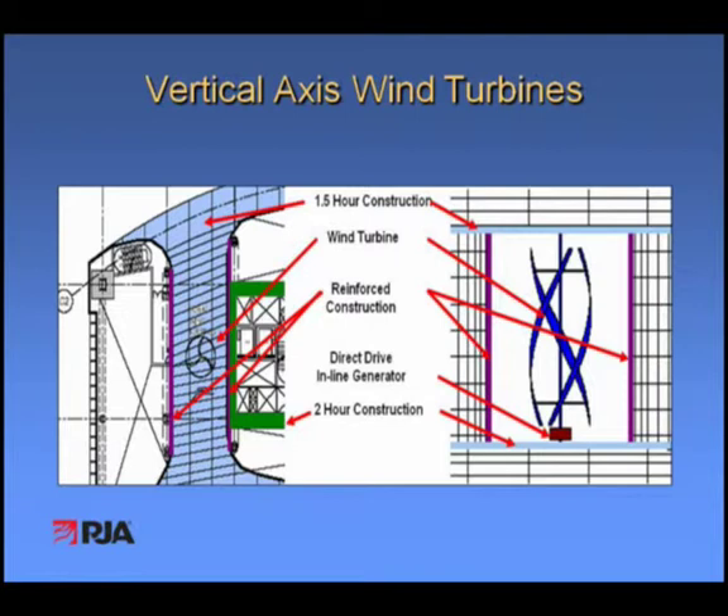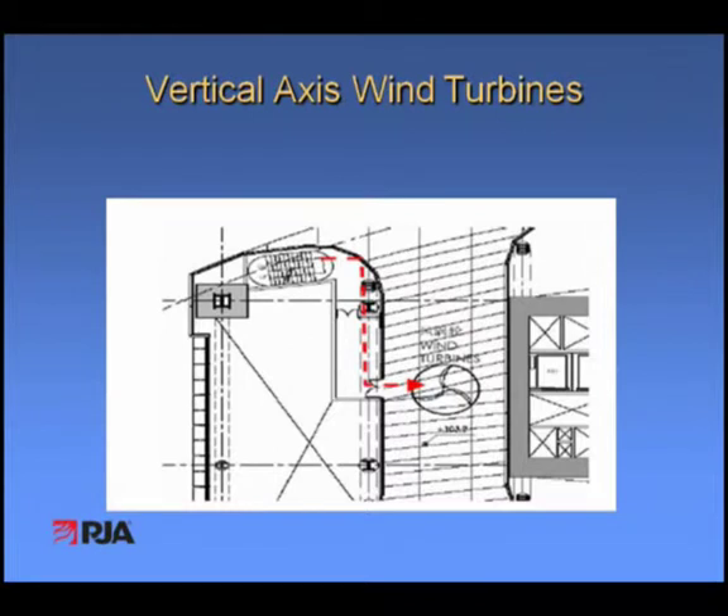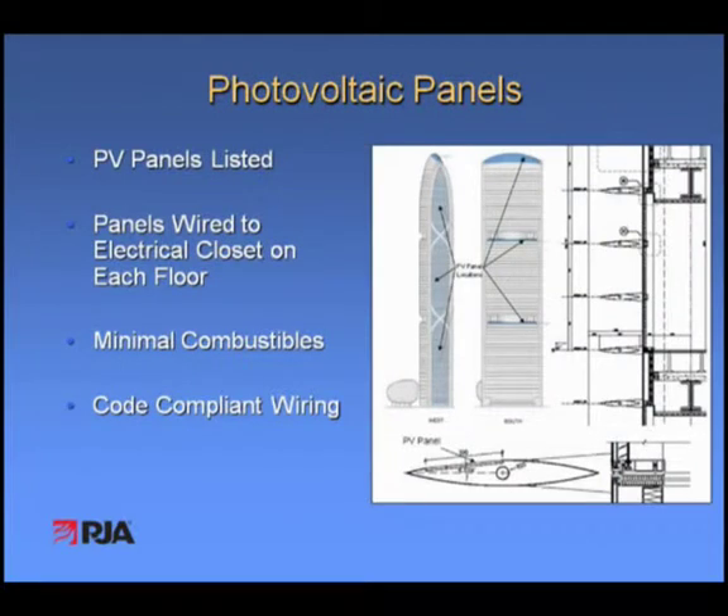They felt pretty satisfied that the components and the device itself were acceptable. The issue then got into protection of the exterior building area around the device. We recommended a strategy with fire-rated floors above and below, and some level of fire resistance reinforcing the fire separation of the exterior wall at the wind turbines, which satisfied their concern. They also wanted access to these things — to be able to fight a fire or handle other failure modes — and we provided for that through one of the exit stairs in each case so they could reach and access the wind turbines. The second issue was the photovoltaic cells — really the same exercise. They looked at the materials, electrical components, and all those sorts of things, developing a brief for the fire department. The wiring and electrical aspects were all compliant with the Chinese code, so we were able to gain approval of this element as well.